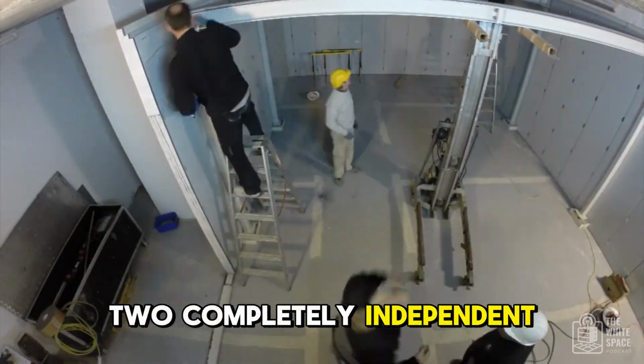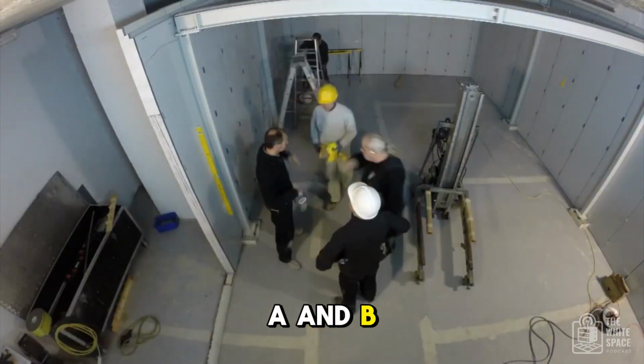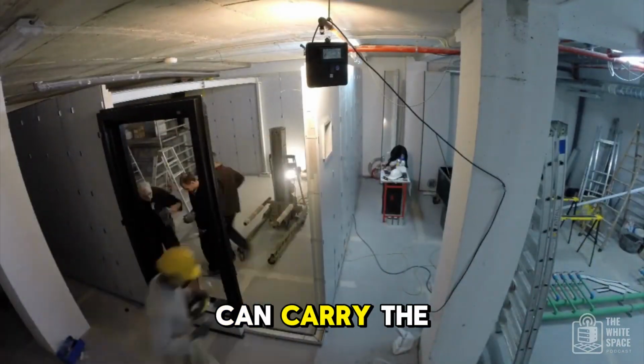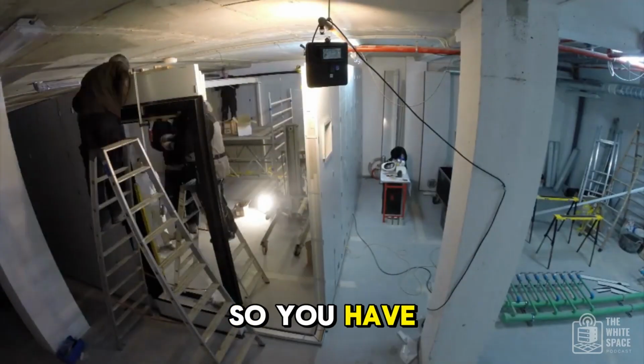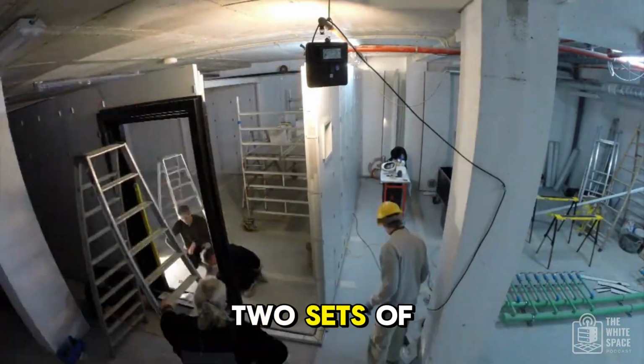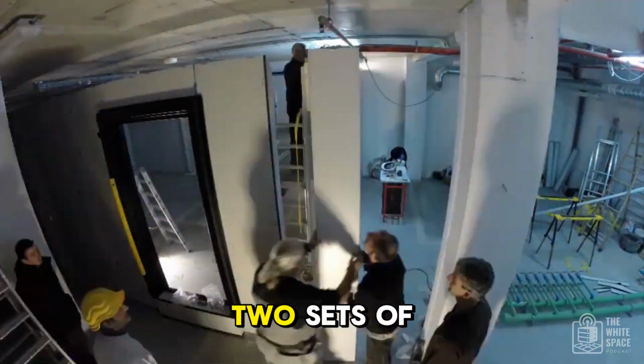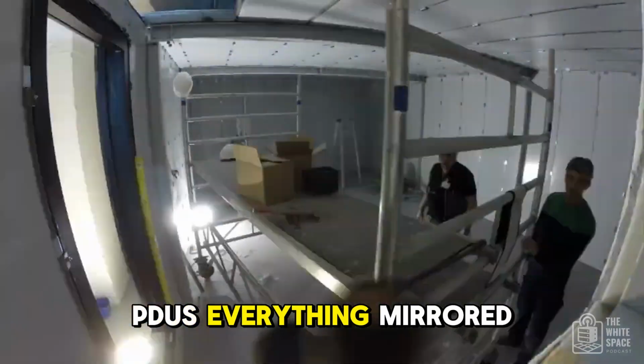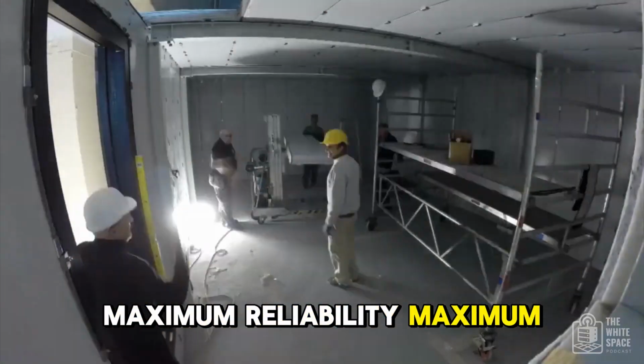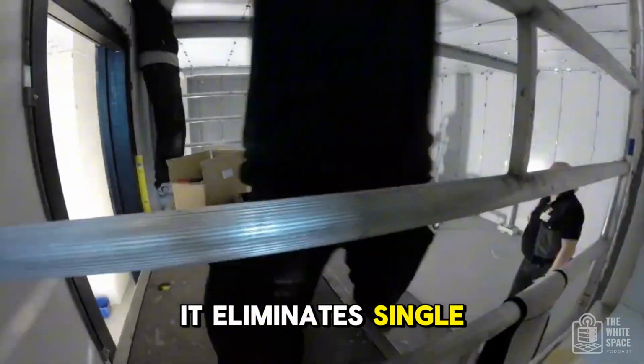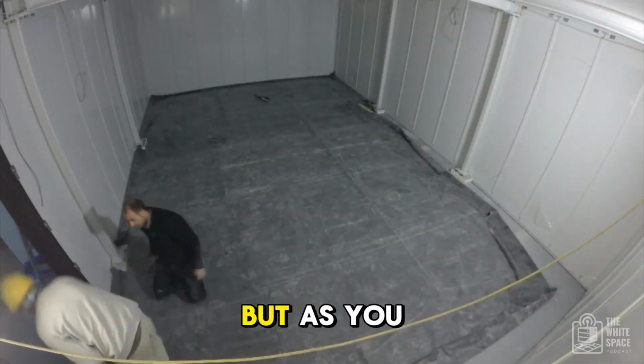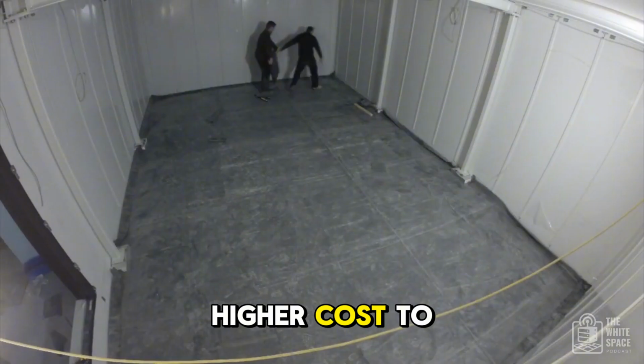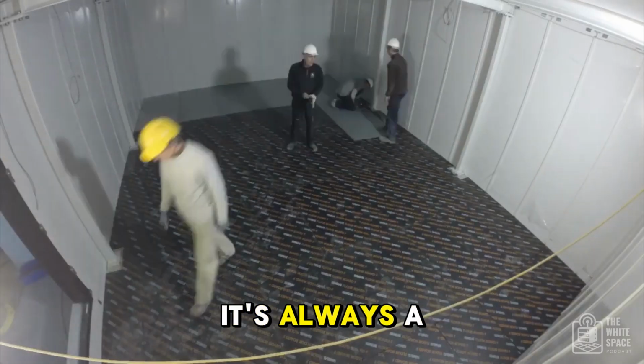2N is full duplication: two completely independent systems, A and B. Each system, N, can carry the entire load on its own. So you have two separate utility feeds, two sets of generators, UPS, and PDUs - everything mirrored. Maximum reliability, eliminating single points of failure entirely. But as you can imagine, it's much higher cost to build.